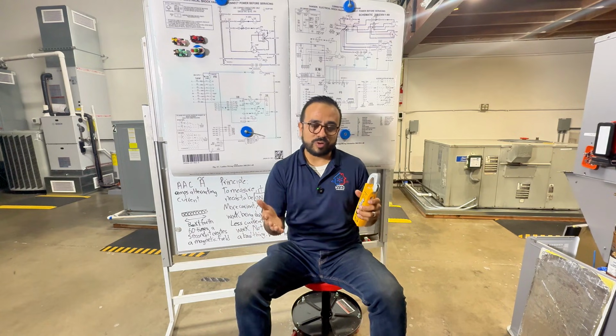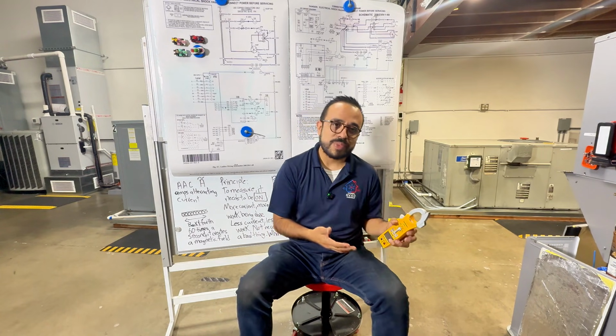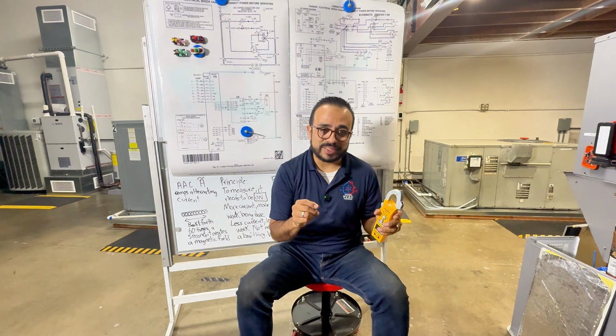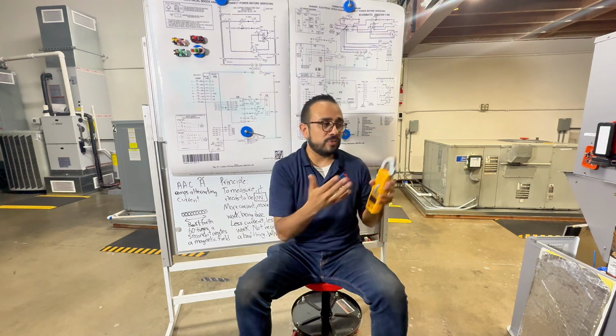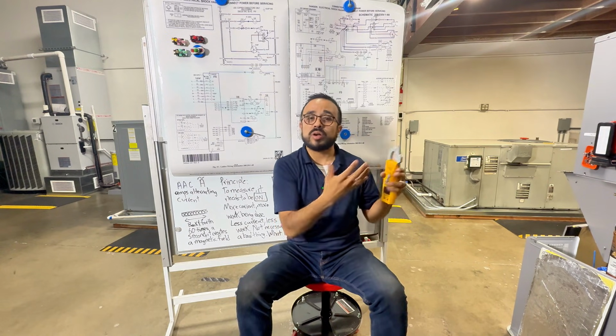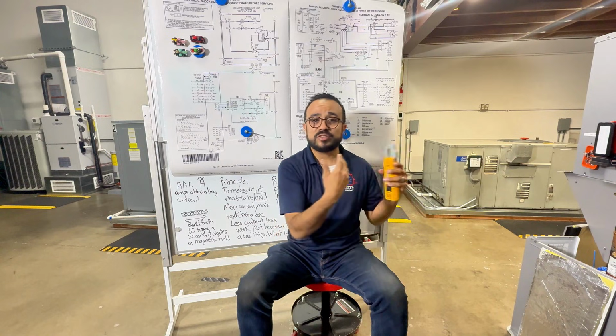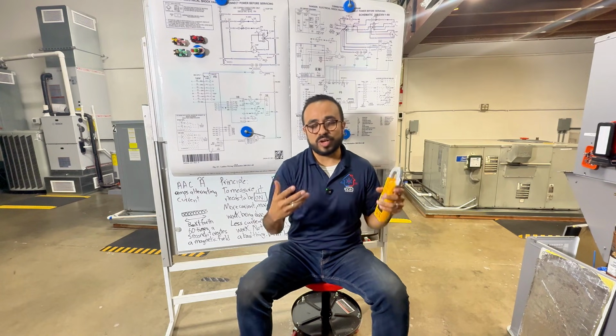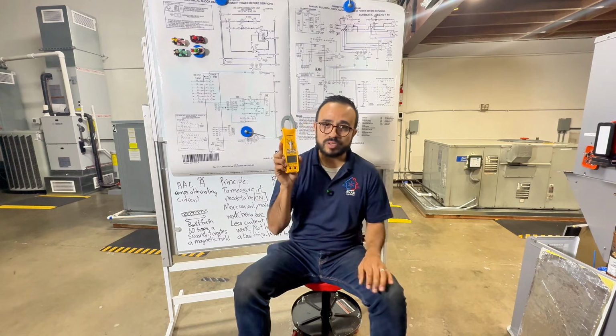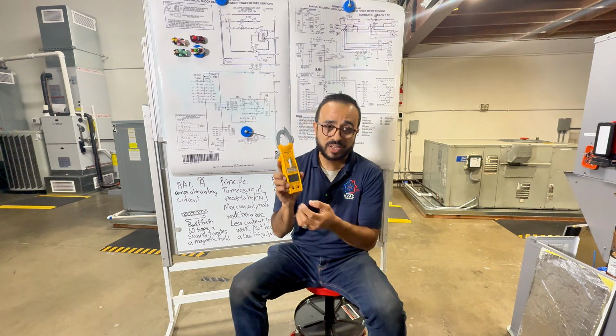Part 1, we went over voltage, potential difference. Part 2, we went over resistance, ohms. And part 3, we're going to be focusing on current, checking amp draw of loads. Things that turn on like compressors, condenser fan motors, anything that is a load. And yes, we're going to be using a meter without test leads.